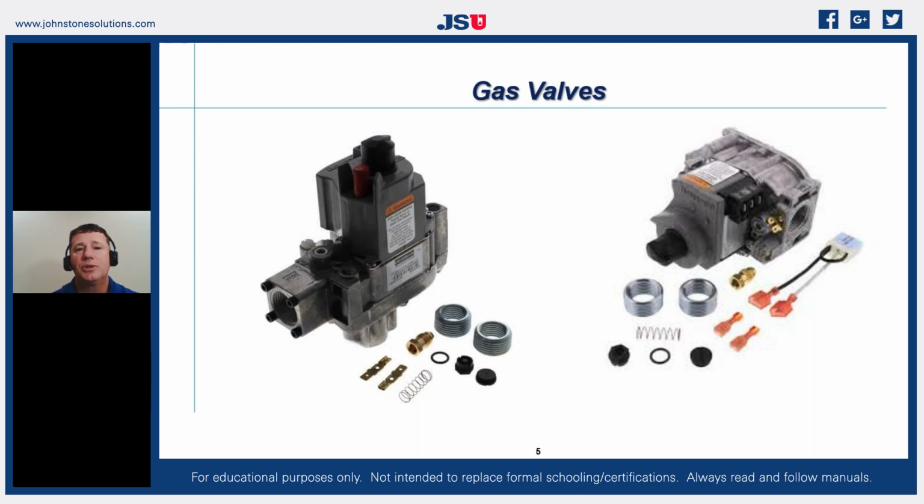So when we get into universal gas valves, if we have a standing pilot system, which I know in residential we're starting to have fewer and fewer of those, but on the commercial side, we still have a lot of standing pilot gas valves. And if you have a universal standing pilot gas valve on your van, you can have a gas valve that can control most. Universal valves are between 50 and all the way up to 250,000 BTU. Some of them will tap out at about 200, but a lot of them will go all the way up to 250,000 BTU capability on that 3/4 inch universal gas valve. That gives you a lot of flexibility on what kind of furnaces you can cover with a single gas valve and how many different manufacturers can be replaced with that one particular one.